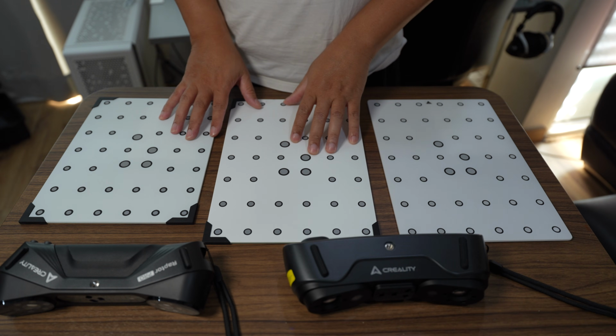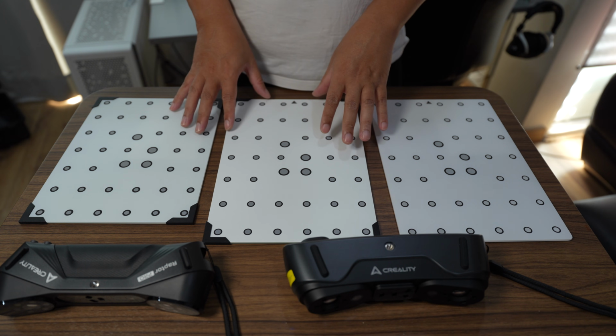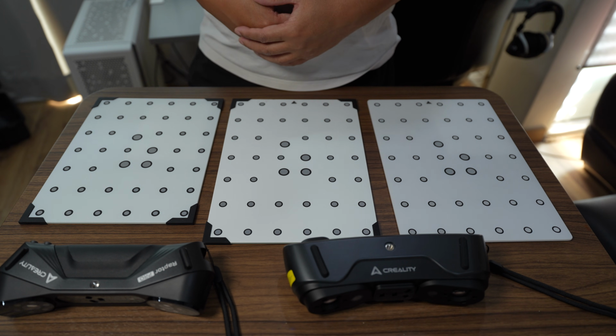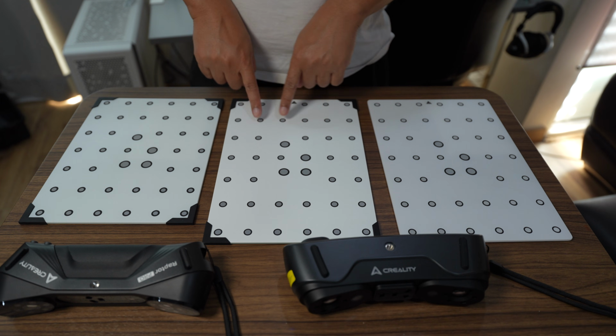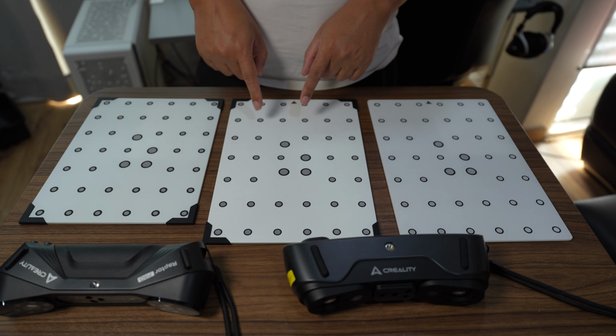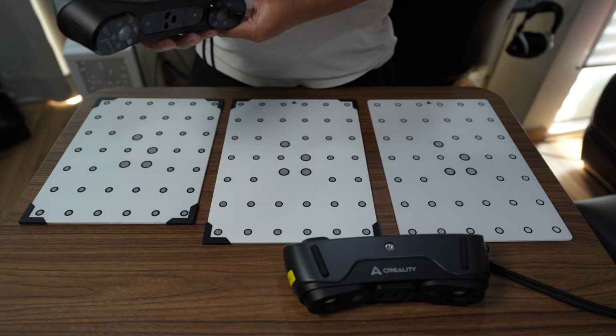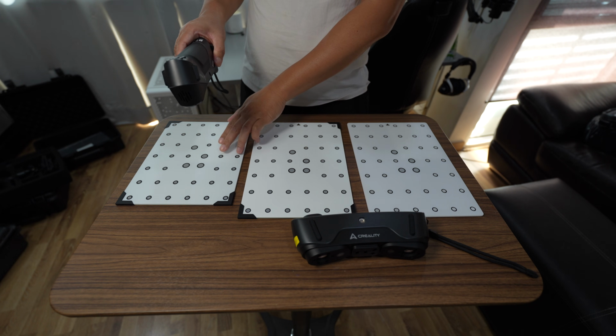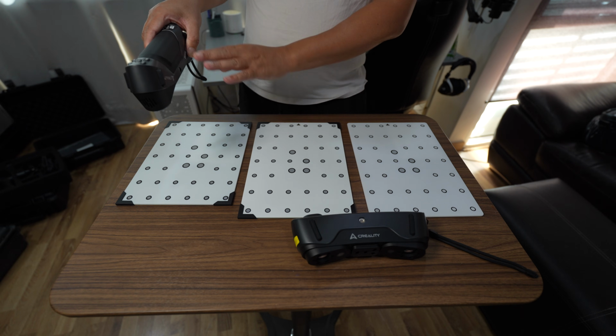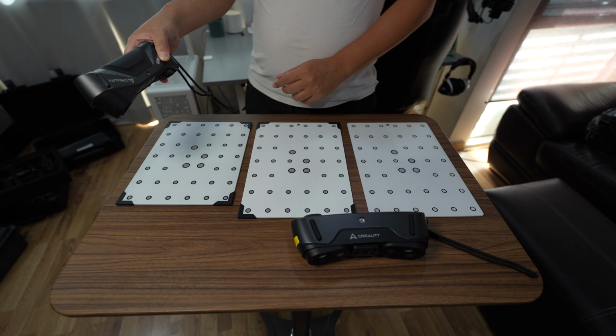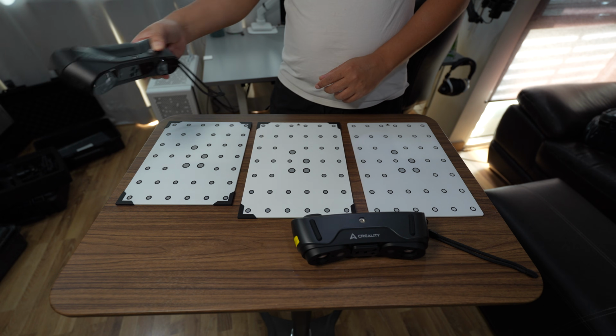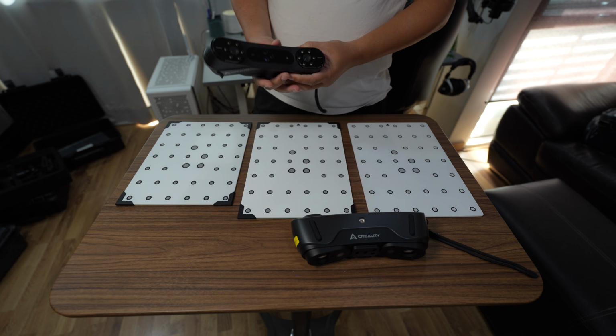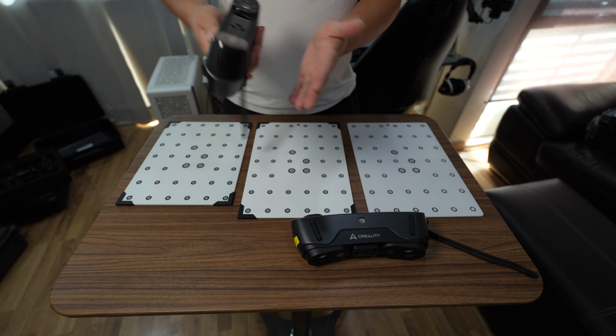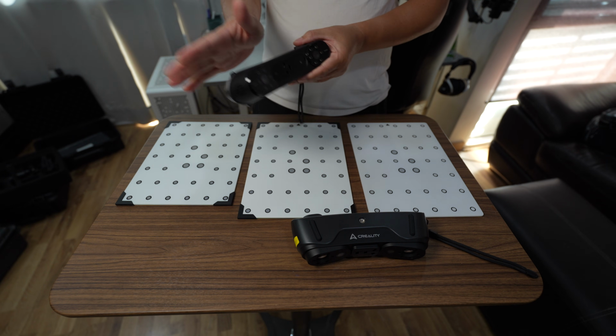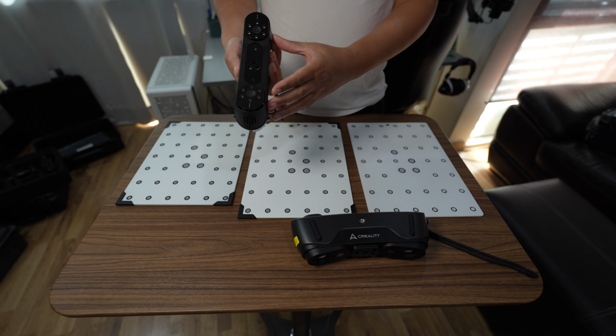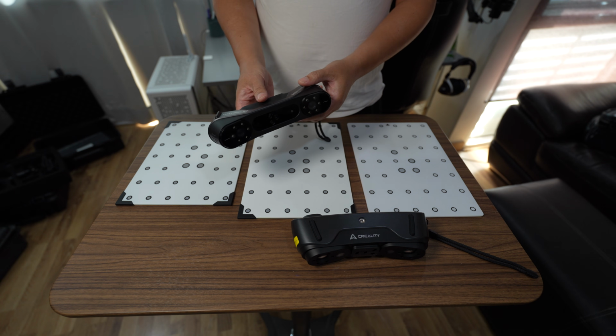The function of the calibration board is to maintain the accuracy of the 3D scanner, not the precision. Because these dots are spaced with a known distance, when you calibrate in the software, it detects the spacing between the dots at different distances from the surface and at different angles, usually 15 degrees on 4 sides. So when you use your 3D scanner for a while, you place it on the table, you knock it accidentally, just a light tap, it's going to move the components inside. It's going to slowly lose its accuracy.